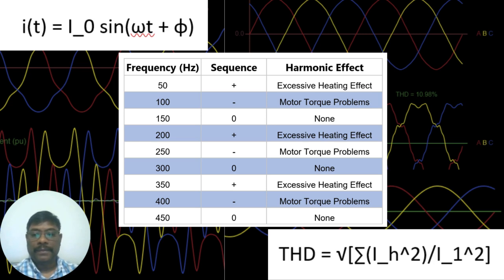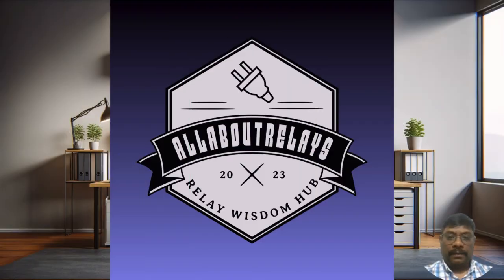Zero sequence causes the current flowing to the neutral wire. That causes heat on the neutral wire and may damage in the long run if it happens. So that's one other thing we need to be very carefully looking into, the total harmonic and fifth harmonics.